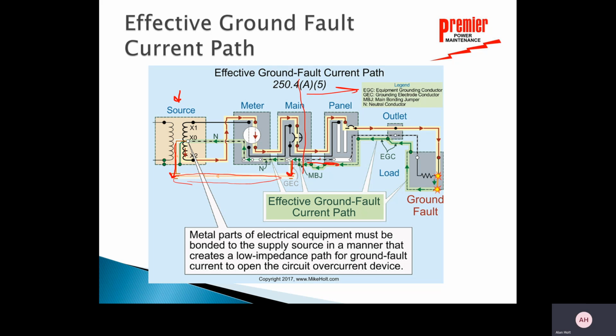Okay, so here's my main bonding jumper where neutral goes to ground. Okay, right here at this location. There's my neutral, there's my neutral, there's my neutral back at the transformer. It's tied to the transformer. That transformer may be 200 feet away. So I have to have the effective ground at my service entrance equipment, my main right here. Some utilities want you to have that in your main disconnect circuit breaker panel. Some utilities do that themselves inside the meter cabinet. That's up to the local jurisdiction.